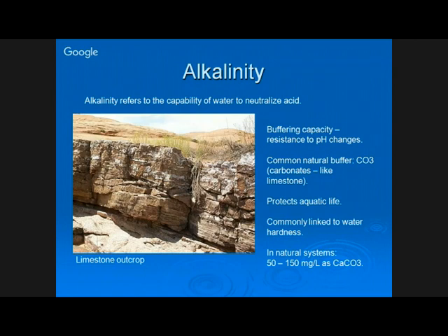And this alkalinity also acts as carbonates and the buffering capacity, the resistance to pH change. If the alkalinity is between 50 to 150, then it acts as a buffer in the natural water. So maintaining this alkalinity between 50 to 150 is also important.